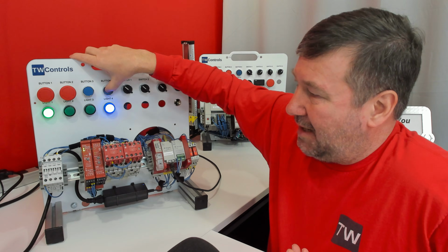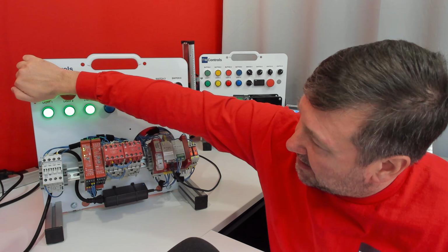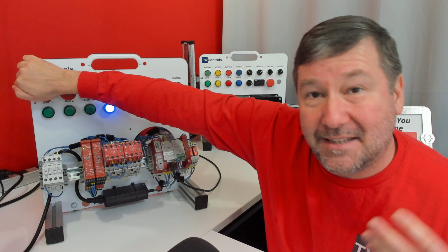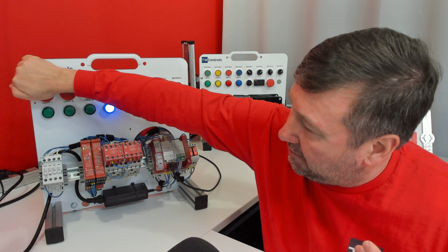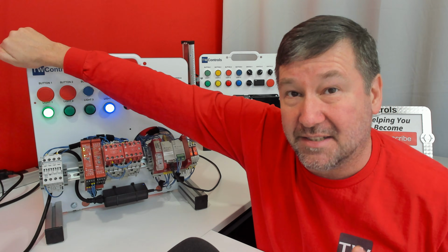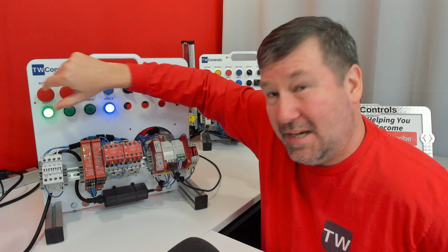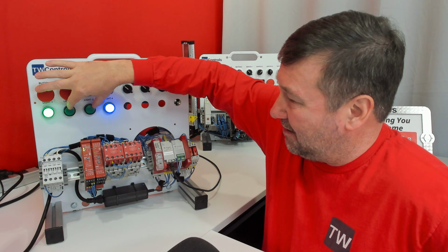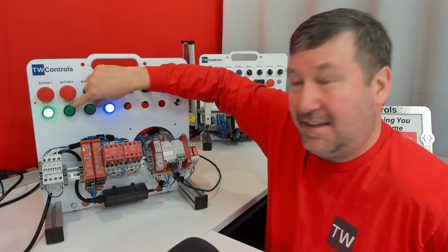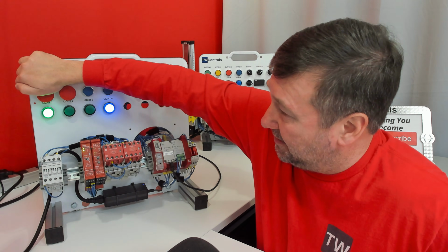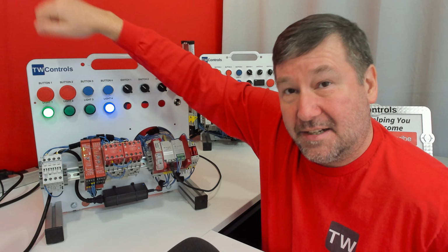But now let's talk about it if an operator is in panic mode. And they run over to press the E-stop, and they don't get it all the way pressed. So now as their hand slides off of it, their machine is going to take back off. So we can't count on this twist being our reset. And you can tell that these two are accounting for that because they have the separate reset here and they did not come back on. But this one, if the operator doesn't get it pressed all the way in, it's going to take back off.